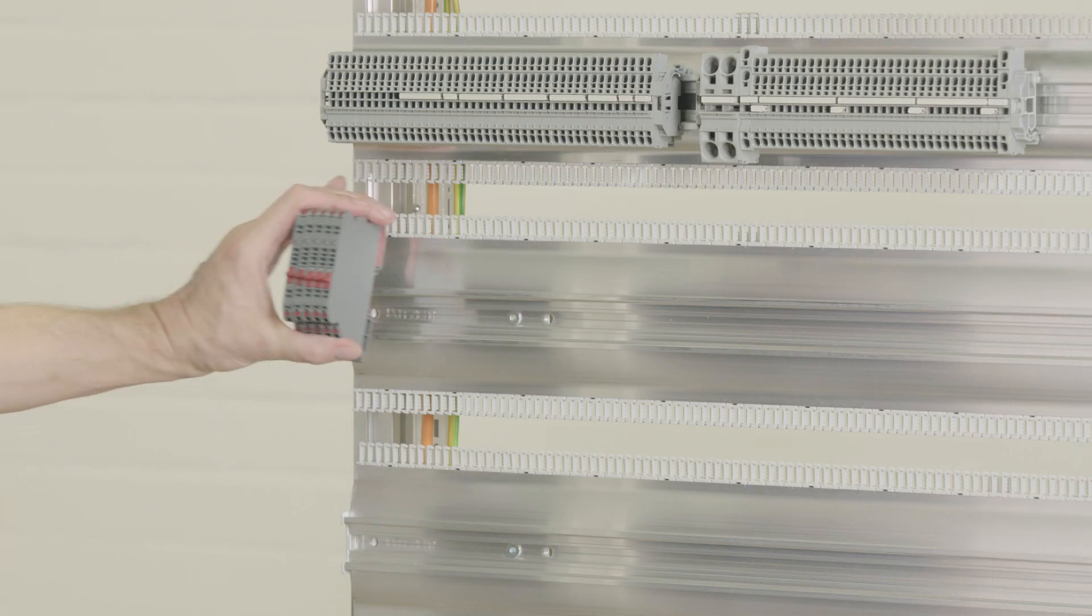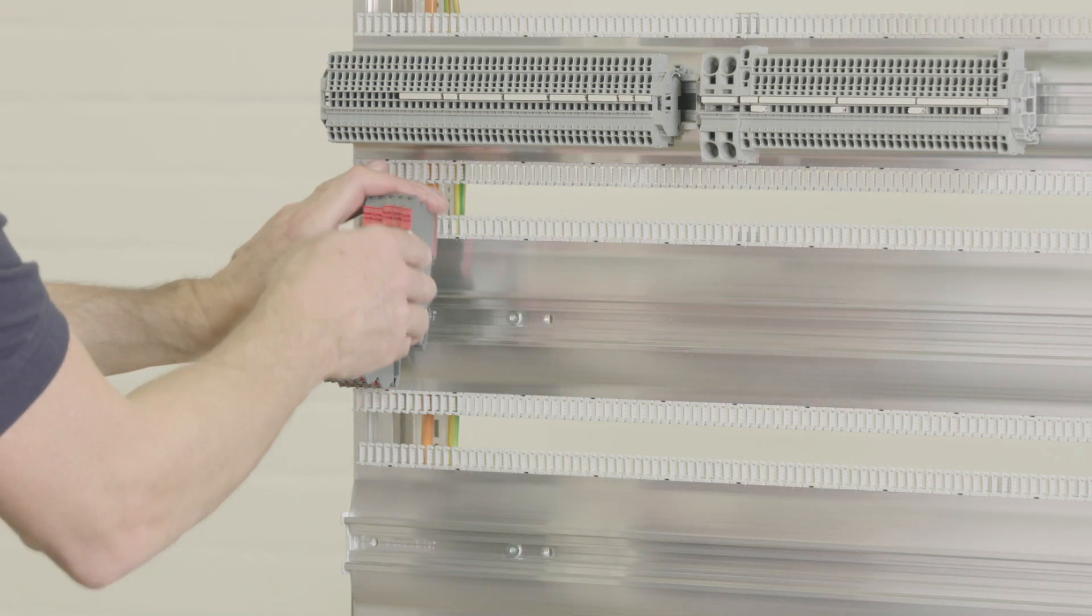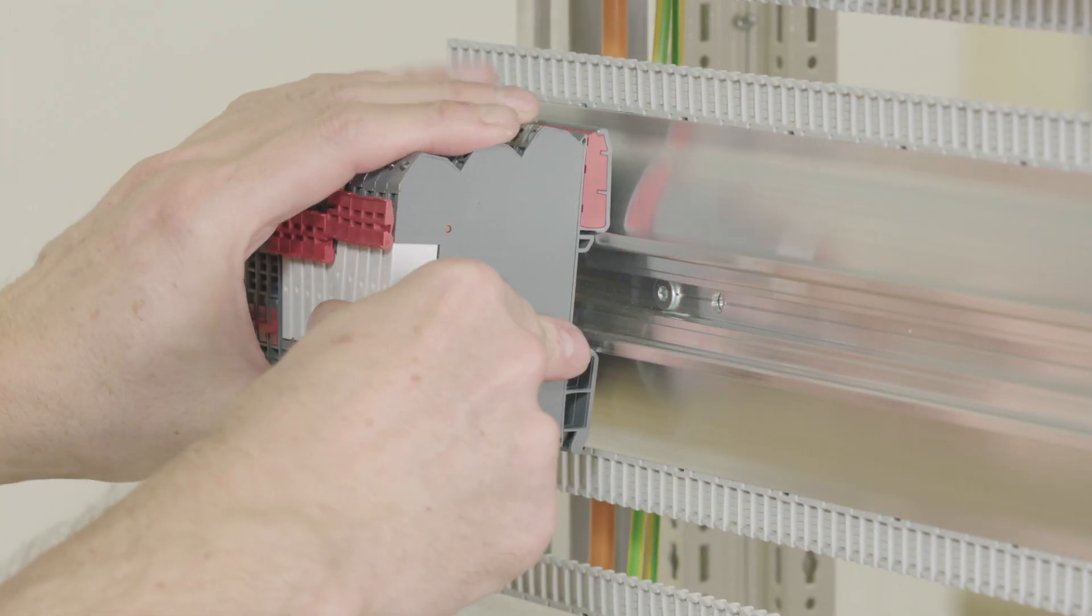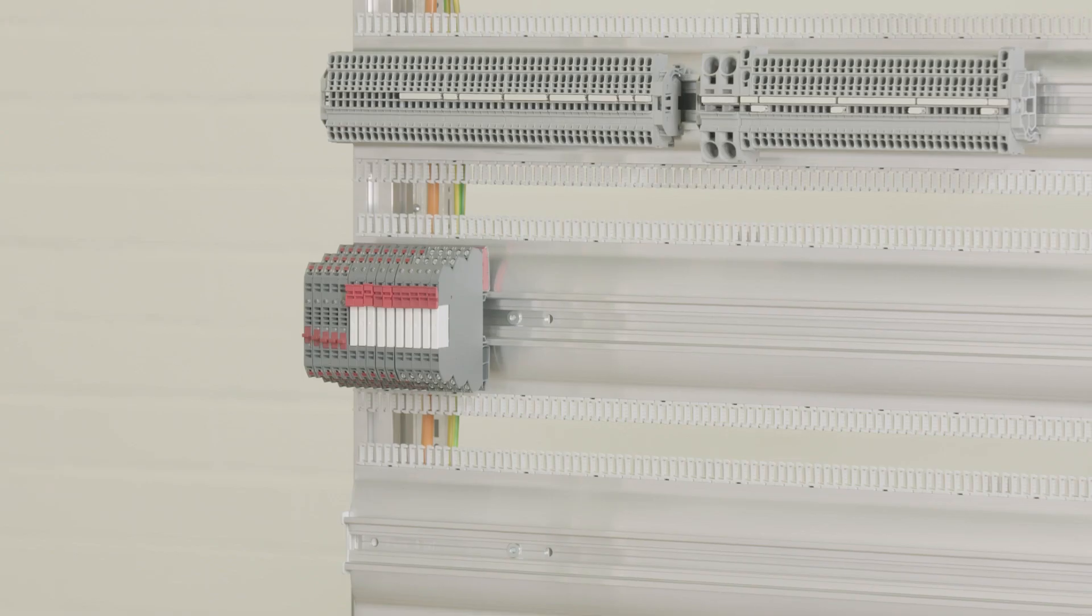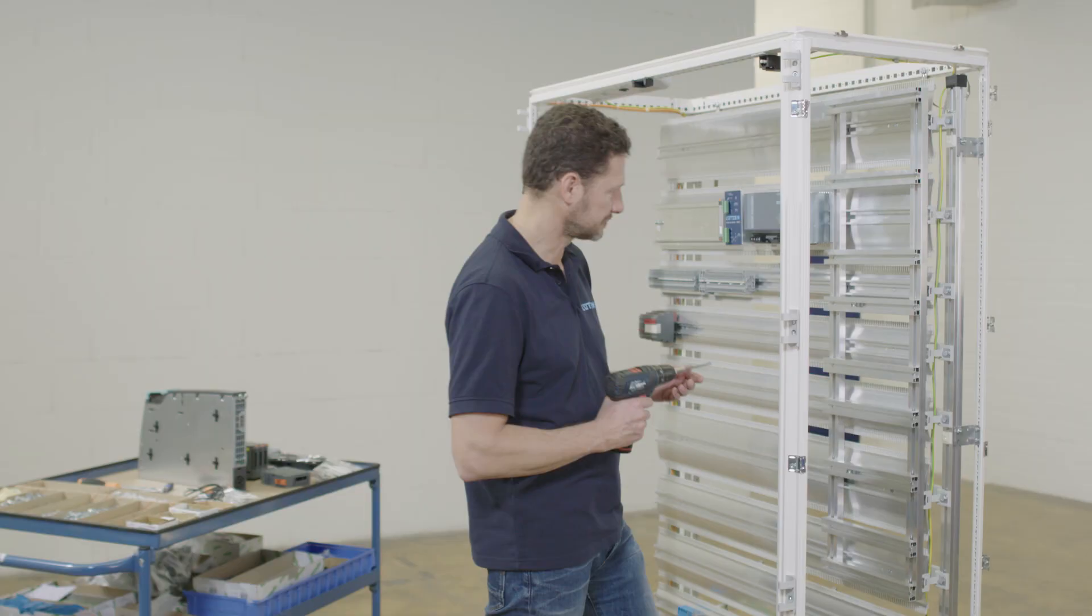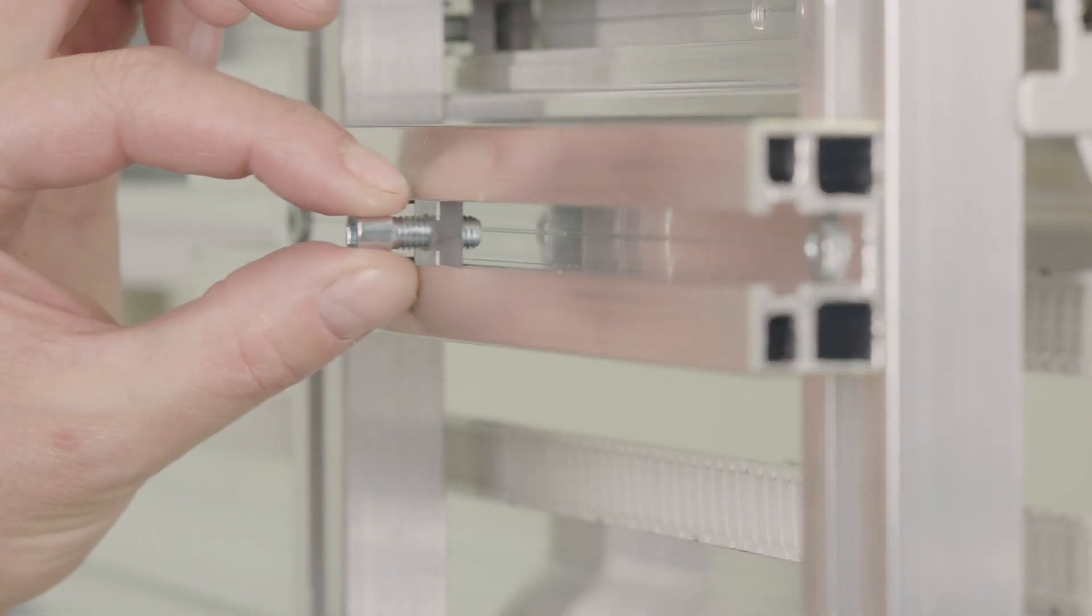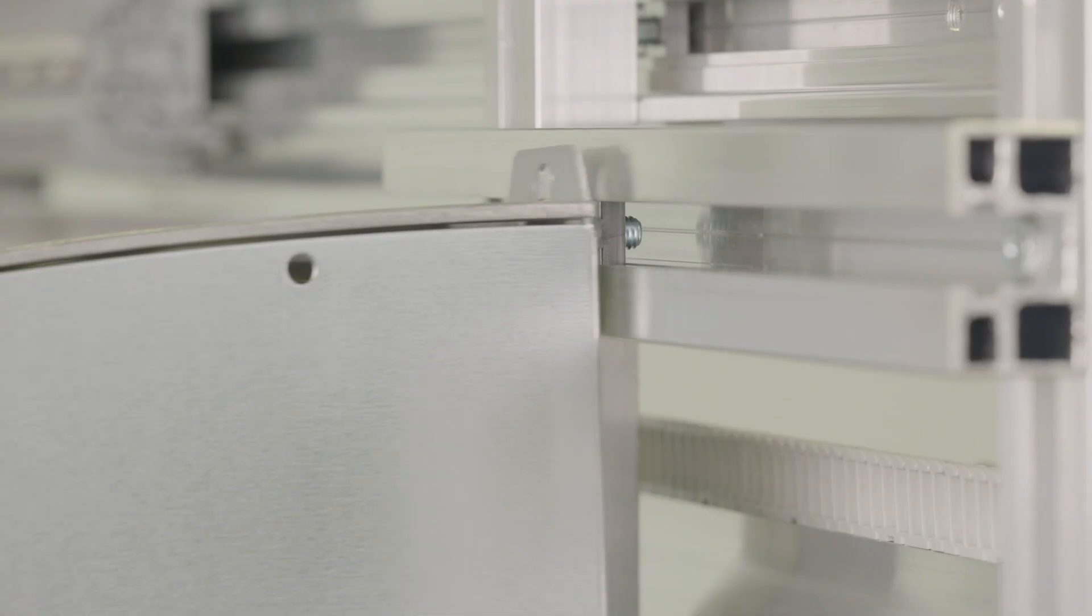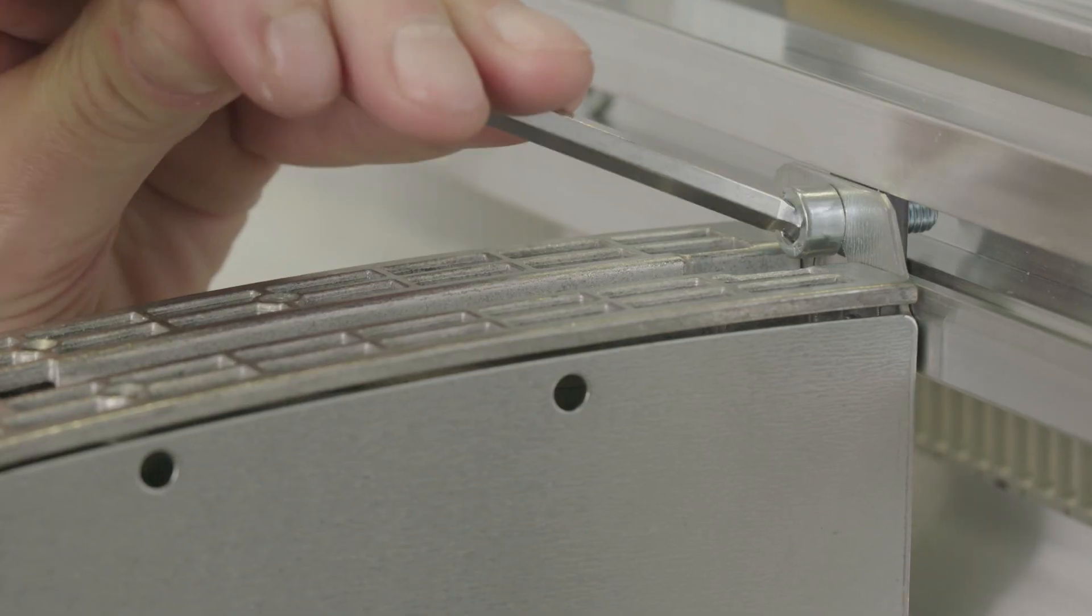The availability of aluminum profiles at differing heights allows the system to be adapted to the components. This allows the space to be utilized far more efficiently and offers a solution for almost all control components. All types of profiles have sliding nut channels which makes it possible to screw or hang the components effortlessly. Heavier components can also be fixed via adapter rail and the weight can be distributed over several modules.